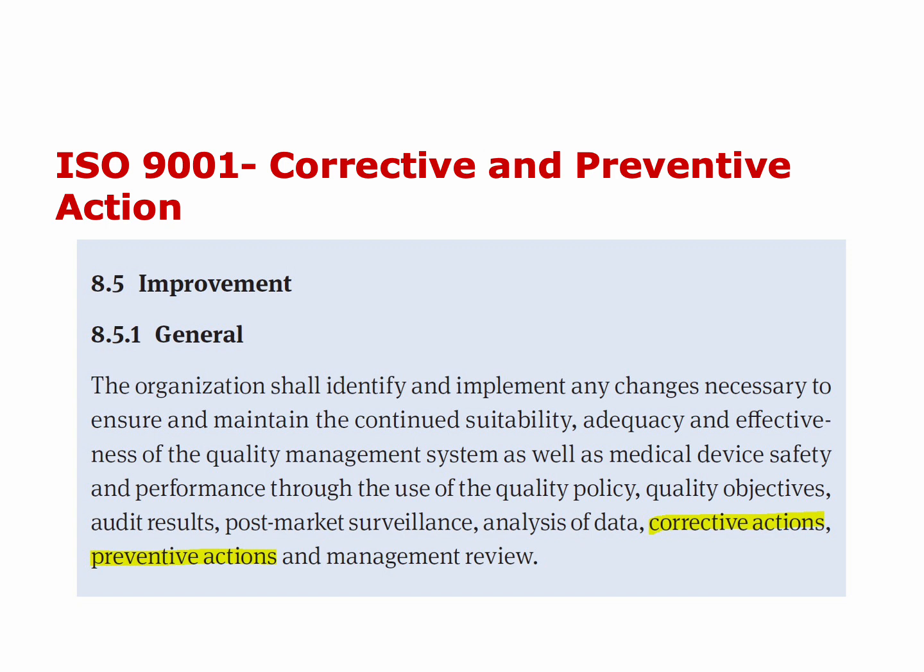Another important fact that we see here, the requirement, is corrective actions. Corrective actions means that when we are looking into any incident, any complaint, for example, any warning letter that we receive from FDA, we will need to do the analysis of that complaint, that issue that we receive. We need to do what we call a root cause analysis in order to understand the root cause of that issue.